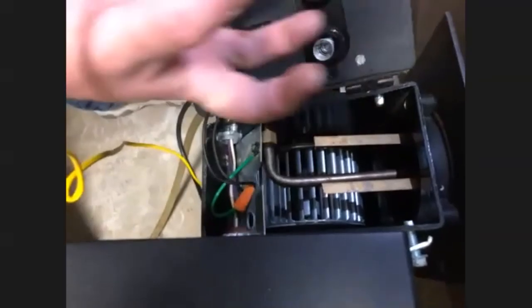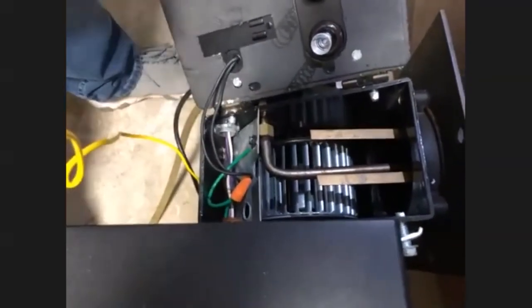You need to be careful because it is inside a tube and it has spacers that locate it accordingly. So it may actually be better to pull it through the inside of the tank. It'll loosen and go all the way inside the tank. You pull the gun assembly out, and you can see the tip of the gun assembly right there.